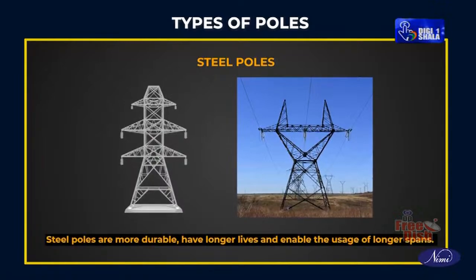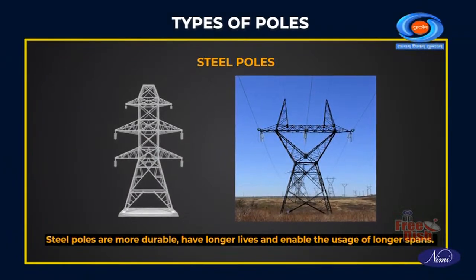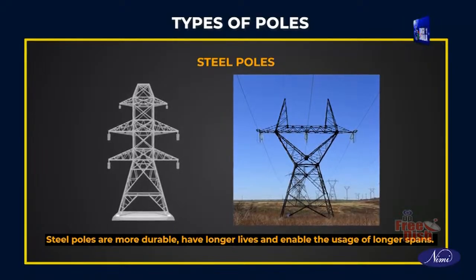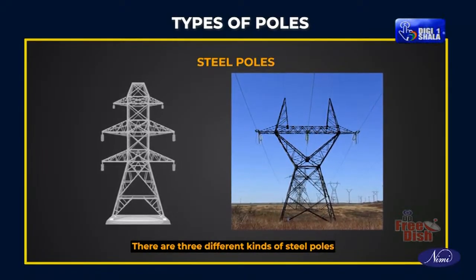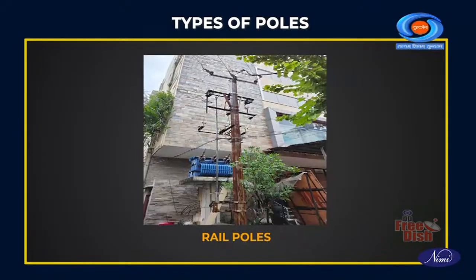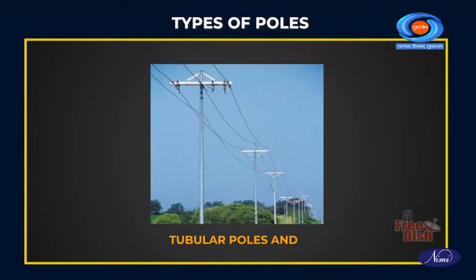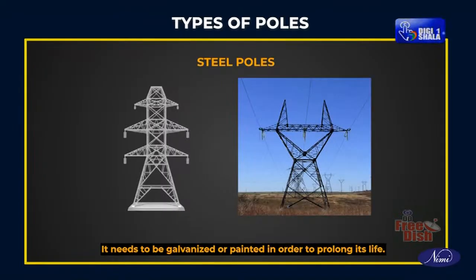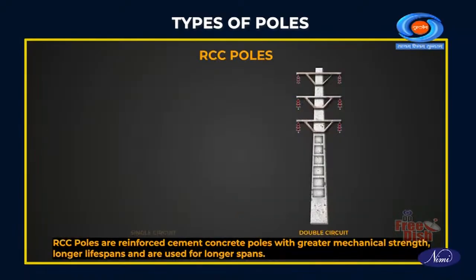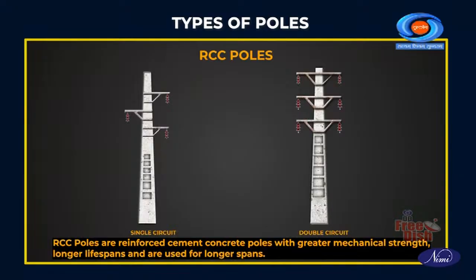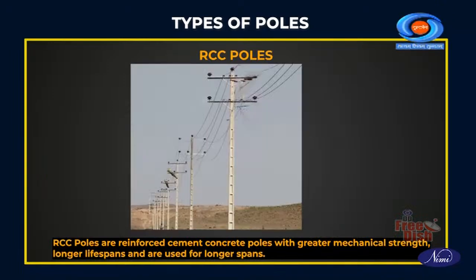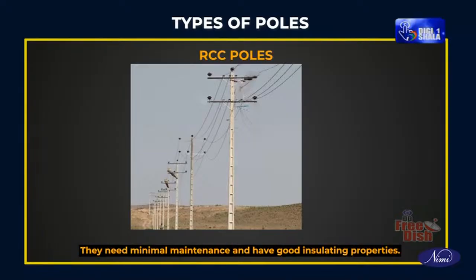Steel poles. Steel poles are more durable, have longer lives and enable the usage of longer spans. There are 3 different kinds of steel poles: rail poles, tubular poles and rolled steel joist. It needs to be galvanized or painted in order to prolong its life. RCC poles. RCC poles are reinforced cement concrete poles with greater mechanical strength, longer lifespans and are used for longer spans. They need minimal maintenance and have good insulating properties.